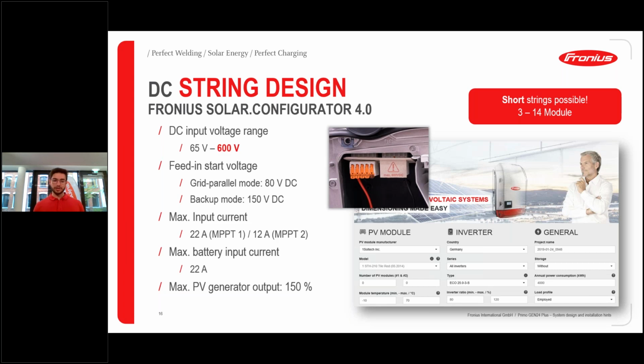Regarding the input current, we have 2 MPP trackers, we already know that, and there are 2 different input currents on those, 22 amps on the first and 12 amps on the second one. And also the battery input has 22 amps, so we can really have high charging and discharging currents with this product. So that's also a huge step upwards.